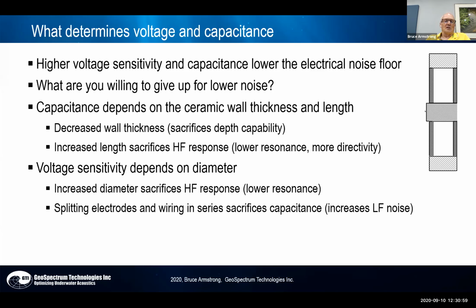You can increase the length of the ceramic, that's feasible, but that sacrifices your high frequency response. You're going to have a lower resonance in your hydrophone, and you're going to get more directivity out of your hydrophone. You can increase the voltage sensitivity by increasing the diameter of the ceramic. But if you do that, your increased diameter sacrifices high frequency response. You get a lower resonance, you have a bigger hydrophone, and so you have diffraction effects sooner.